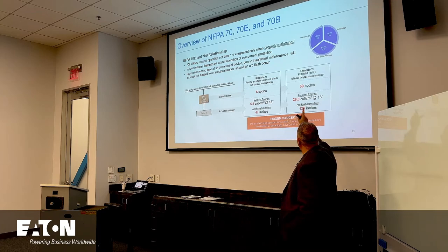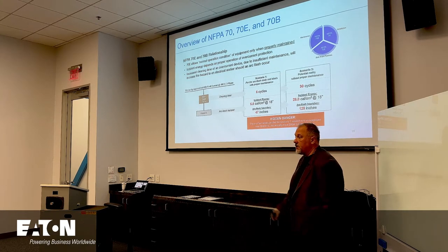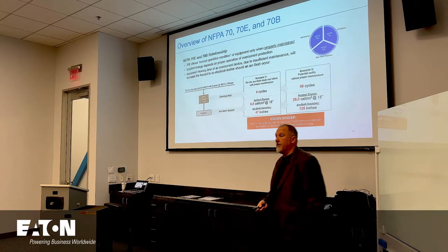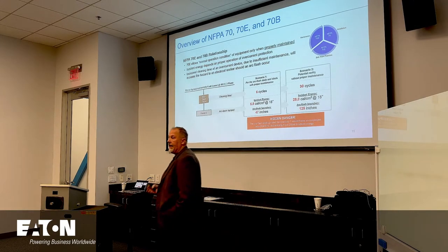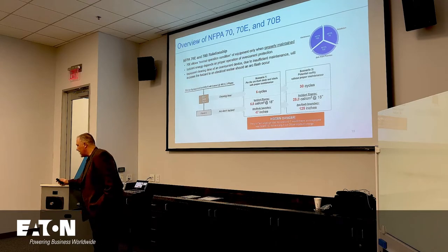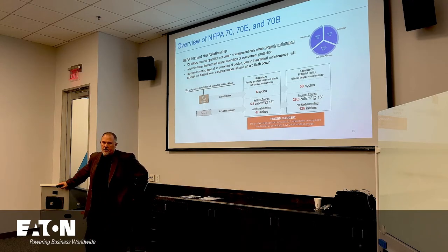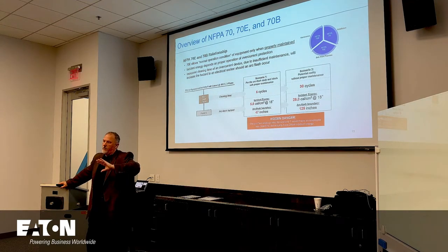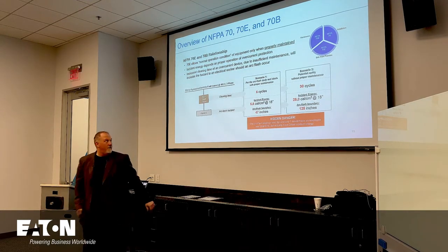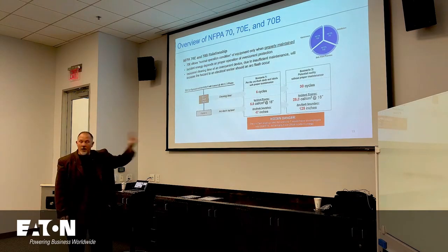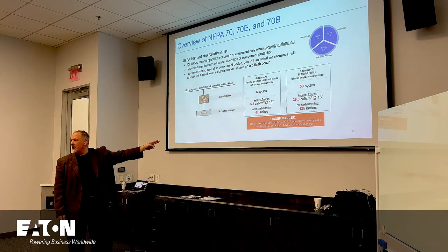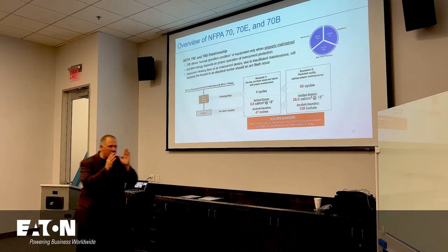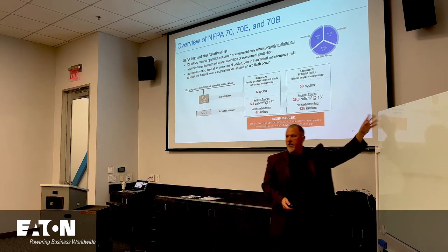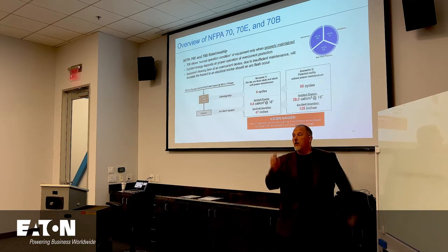So 5.8 calories, if your upstream circuit breaker does not clear, you could have a 29 calorie event and you're dressed for something a lot less, right? There are procedures and processes to handle situations where you don't have maintenance on equipment, which is, again, probably another 8-hour day. But in any case, you're not going to know this. Your electrical worker isn't going to know unless they go to that piece of equipment and look for the information that says it was properly maintained, or they look at your records.